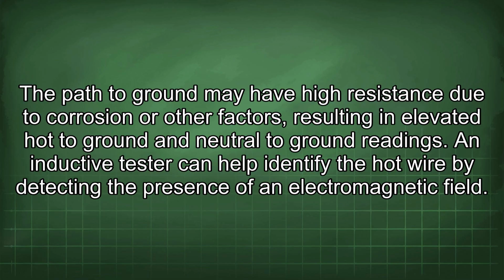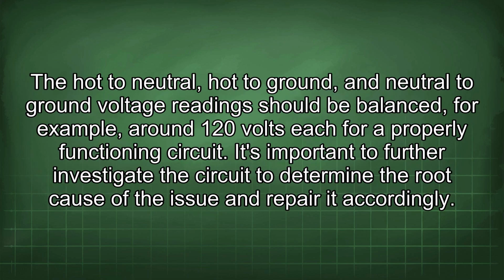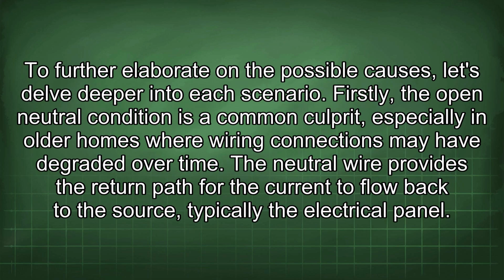An inductive tester can help identify the hot wire by detecting the presence of an electromagnetic field. The hot to neutral, hot to ground, and neutral to ground voltage readings should be balanced, for example, around 120 volts each for a properly functioning circuit. It's important to further investigate the circuit to determine the root cause of the issue and repair it accordingly. To further elaborate on the possible causes, let's delve deeper into each scenario.